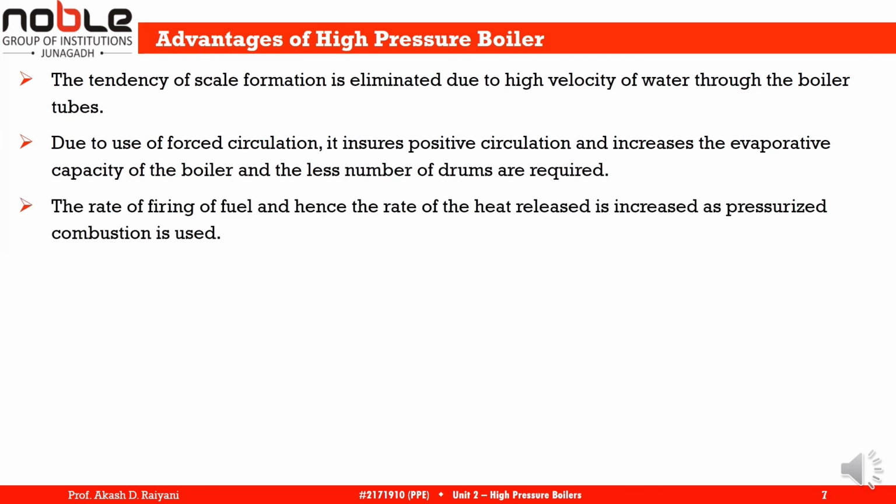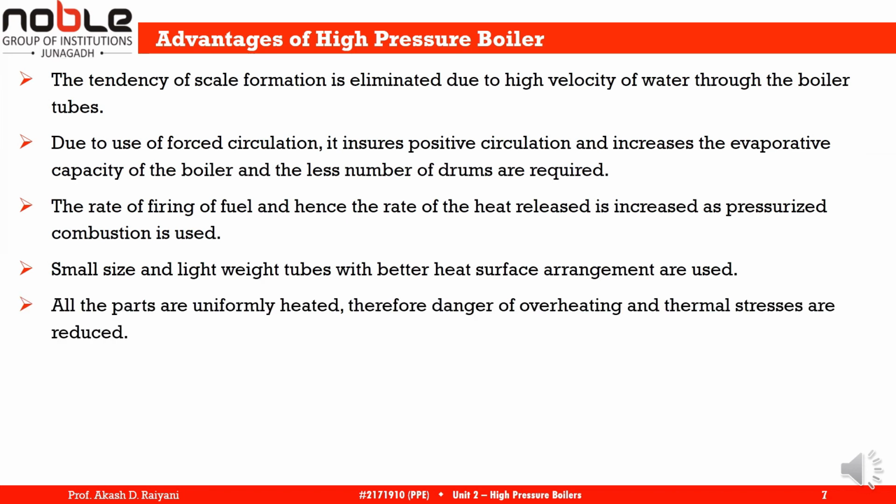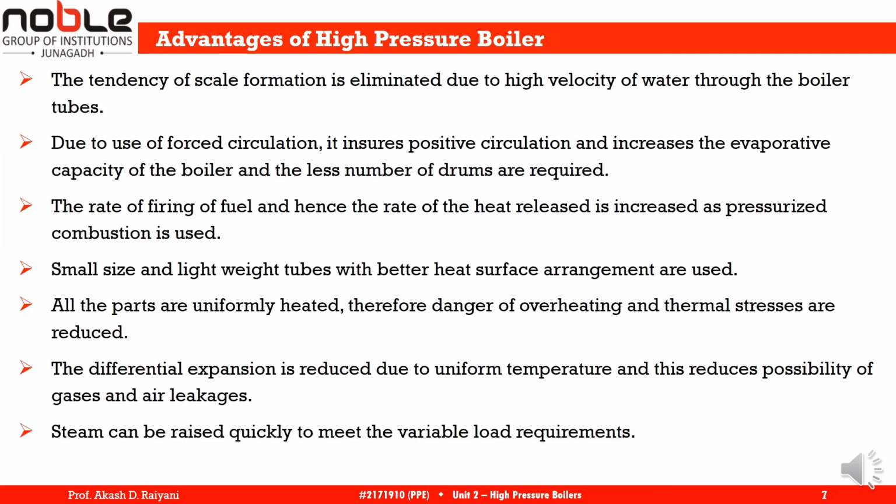The rate of firing of fuel, and hence the rate of heat release, is increased as pressurized combustion is used. Small size and lightweight tubes with better heating surface arrangement are used. All the parts are uniformly heated, therefore the danger of overheating and thermal stresses is reduced. The differential expansion is reduced due to the uniform temperature, and this reduces the possibility of gas and air leakage.